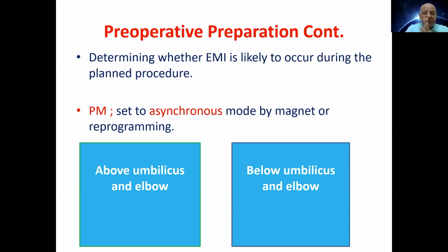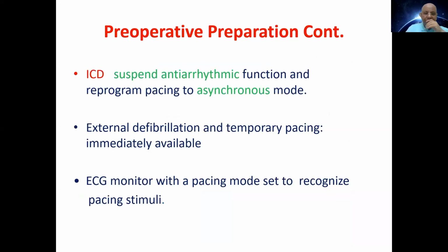Okay, so for a pacemaker, you have to put it in asynchronous mode, either by magnet or by program. If the patient is above the umbilicus, above the elbow, you have to put a magnet on the pacemaker. If below the umbilicus, below the elbow, don't be afraid. You can keep the magnet available. For the ICD, you have to suspend the antiarrhythmia function, and the pacemaker in asynchronous mode. And all the patients must have an external defibrillator and pacemaker outside, and continuous ECG monitoring is mandatory.